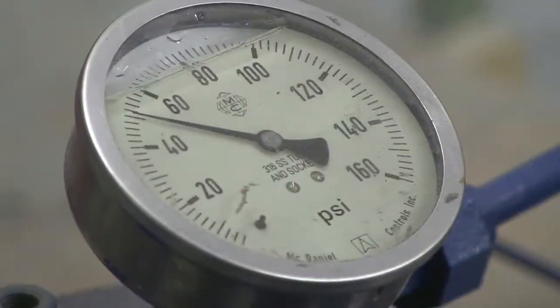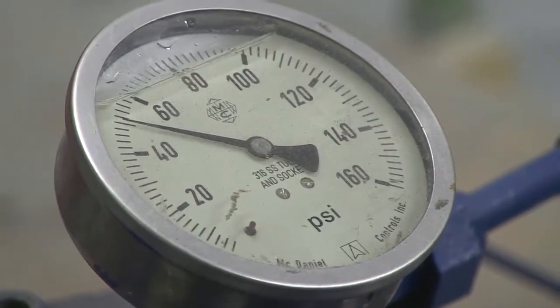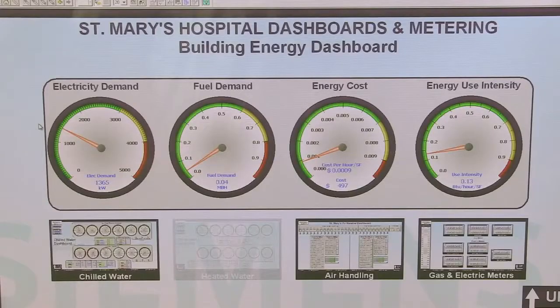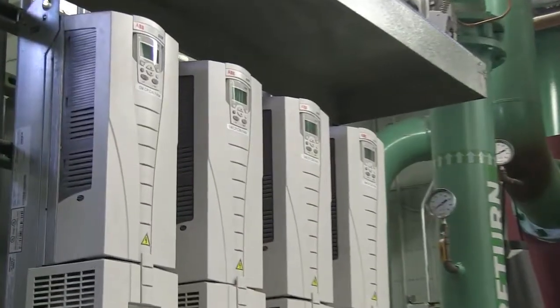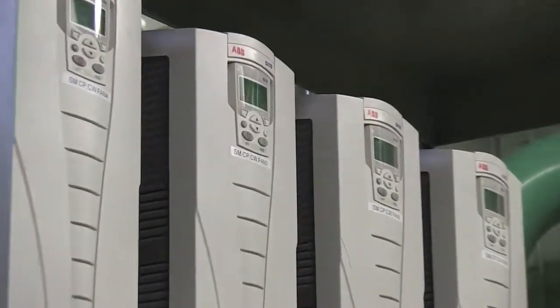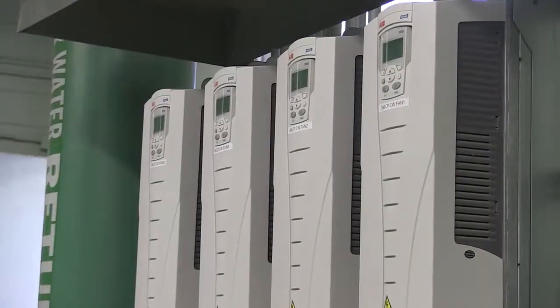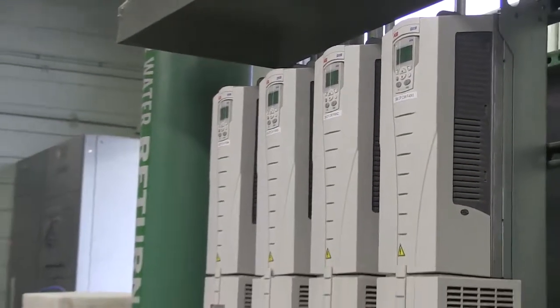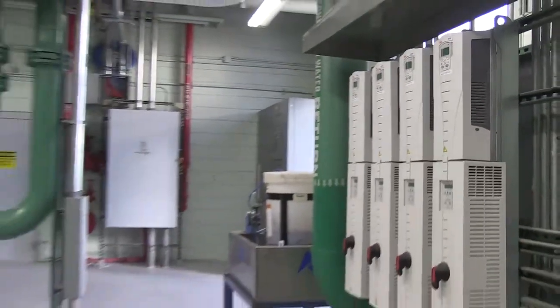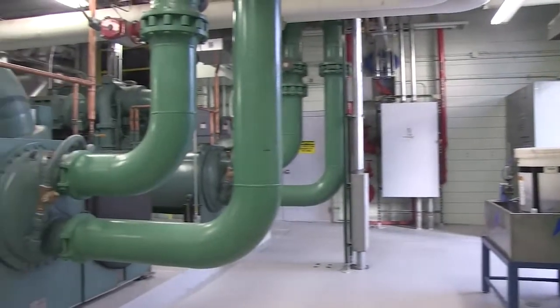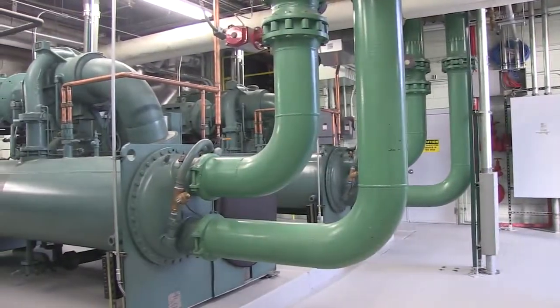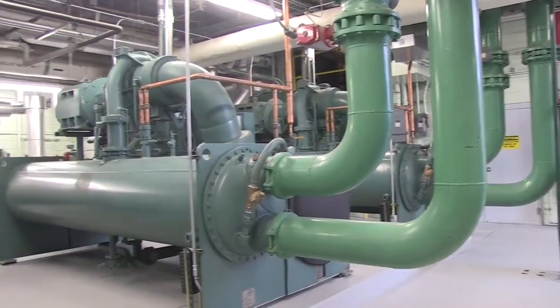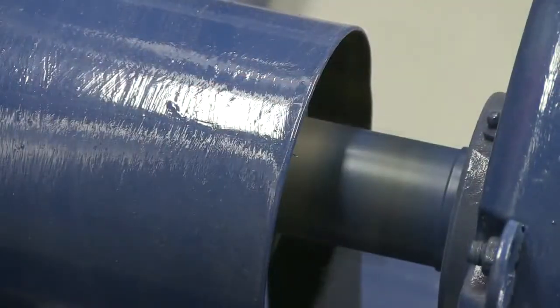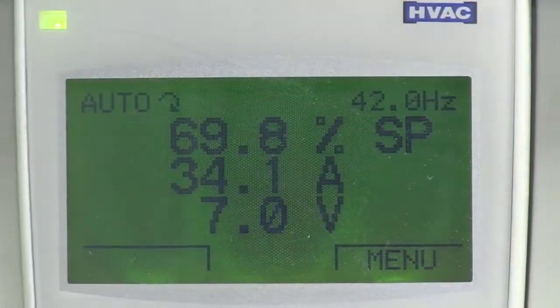It gives us real-time data, allows us to make adjustments in programming that affects patient comfort, and allows us to see when something is out of sequence, which could drive energy consumption up, and allows us to adjust to it. We didn't purchase any new fancy air handlers or equipment. It was essentially a project that made our existing equipment more energy efficient through retro-commissioning.